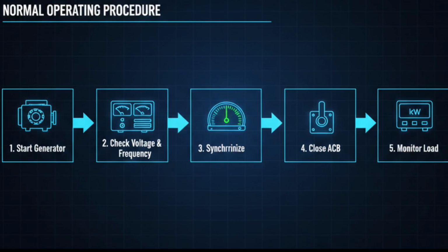Normal operating procedure. Let us understand the normal operating sequence of the main switchboard. First, start the diesel generator and allow it to reach stable speed. Second, check voltage and frequency values. Third, perform synchronization with the busbar. Fourth, close the air circuit breaker. After closing, monitor load distribution carefully.